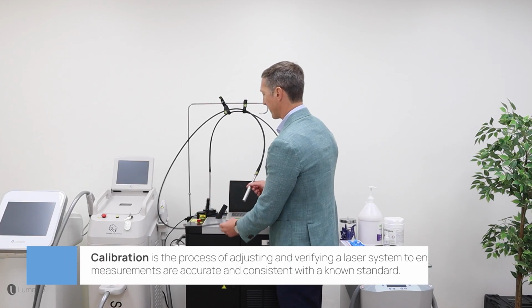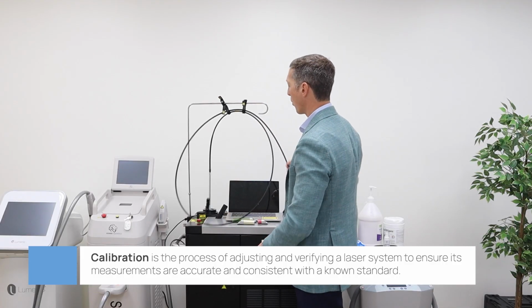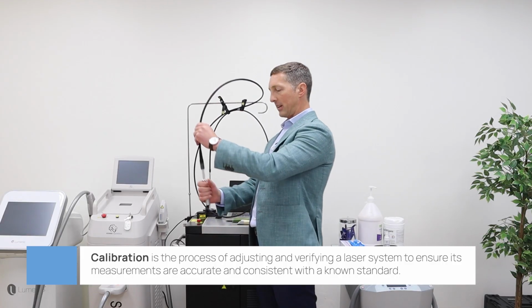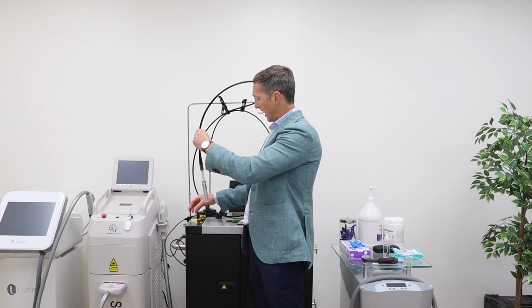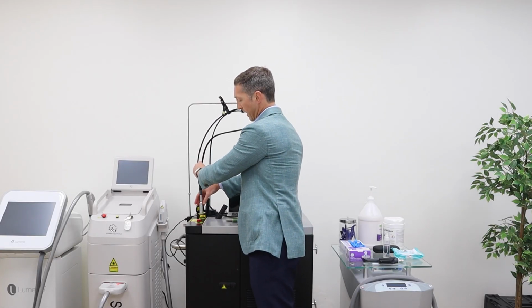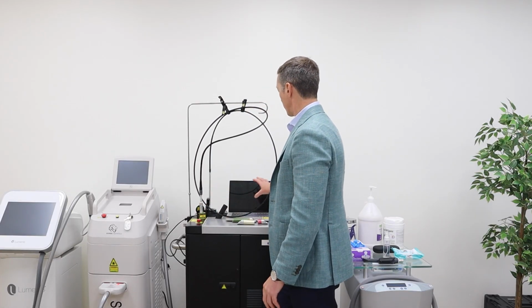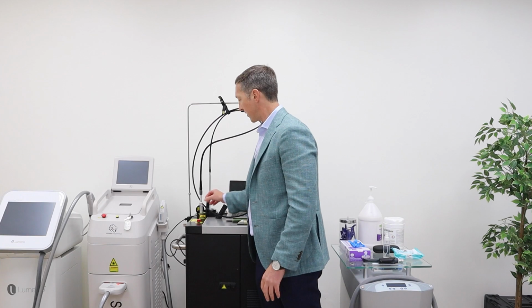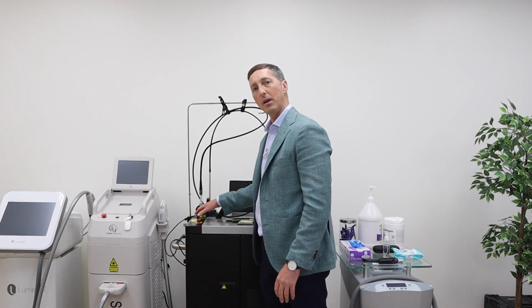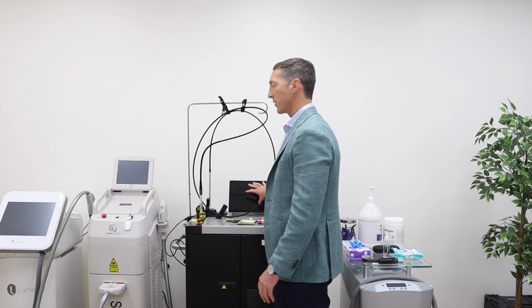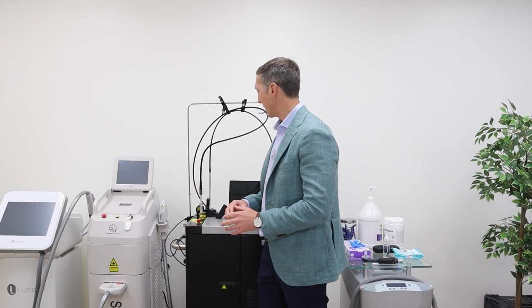So you probably are familiar with the idea that when you start your laser systems up in the morning or you're about ready to go into treatment, you take this thing called a laser aperture and you put it into some type of calibration port, right? And then you start doing a test function. The laser system is going to detect what it's actually putting out and make sure what it's putting out here agrees with your settings here. Basic concept, overly simplified, but that's the idea.